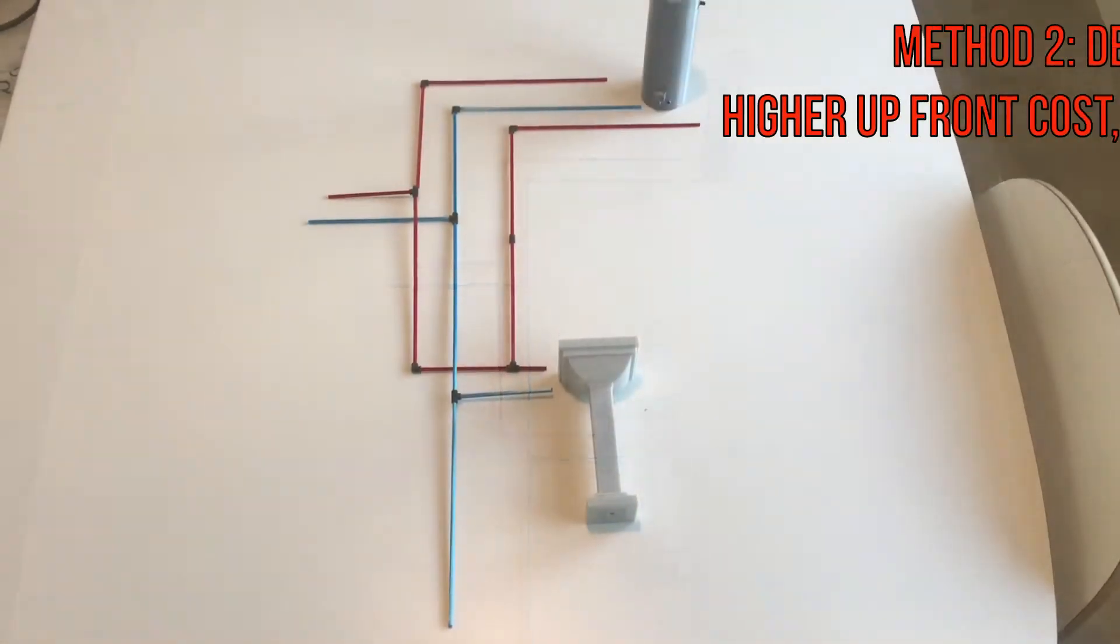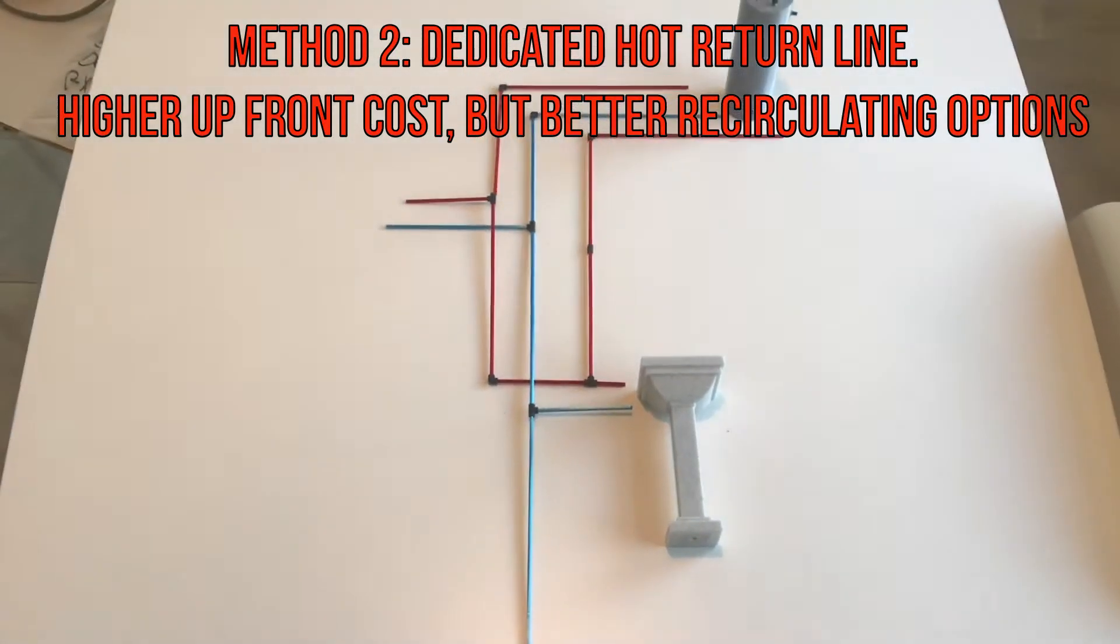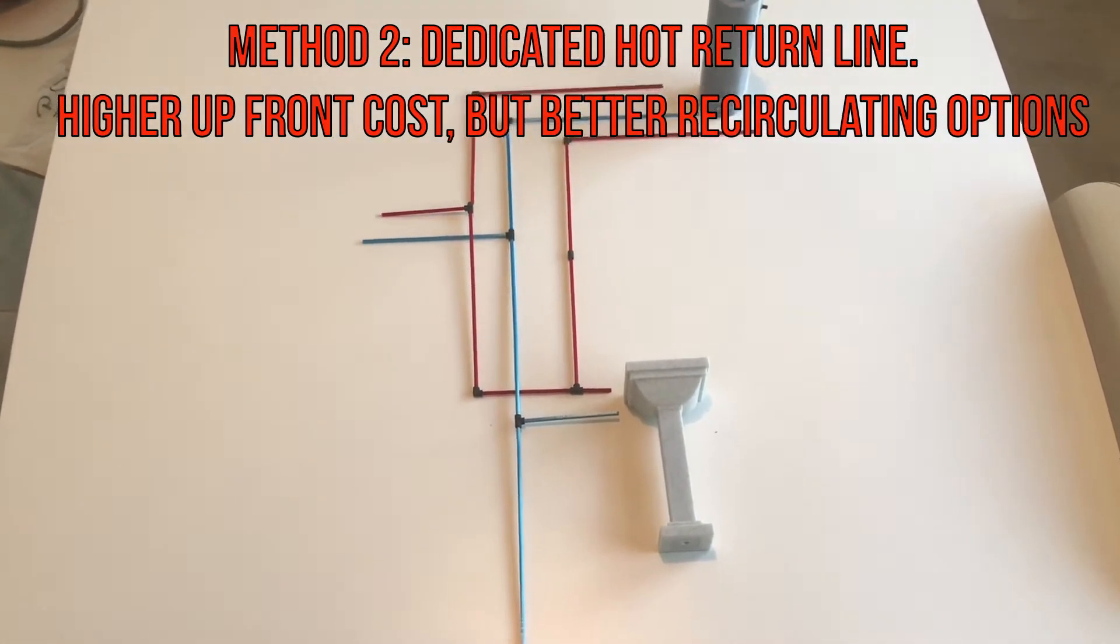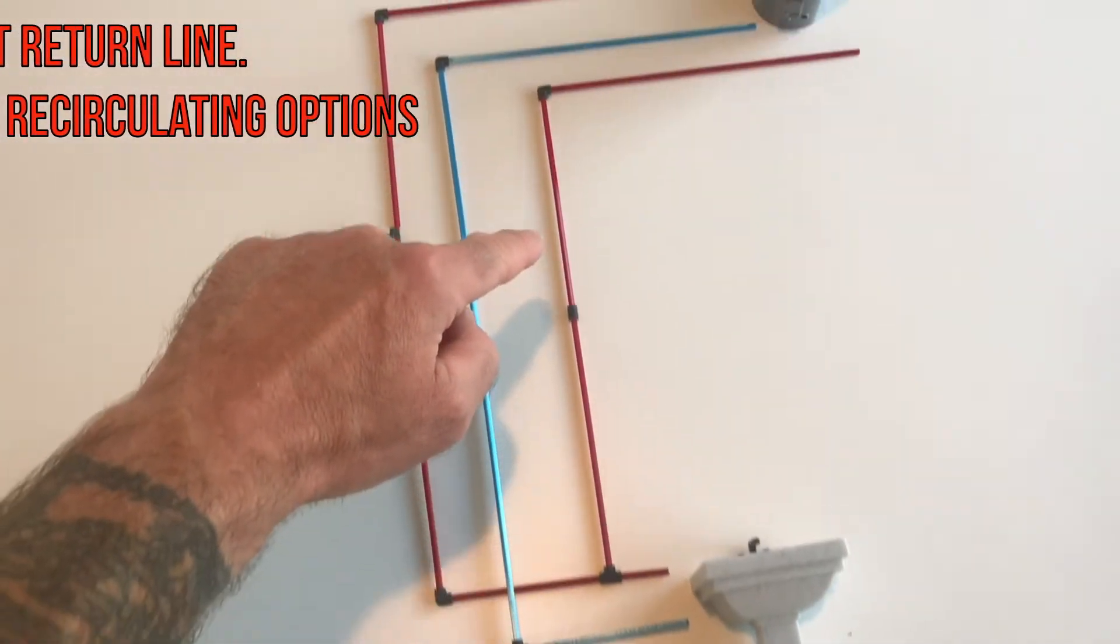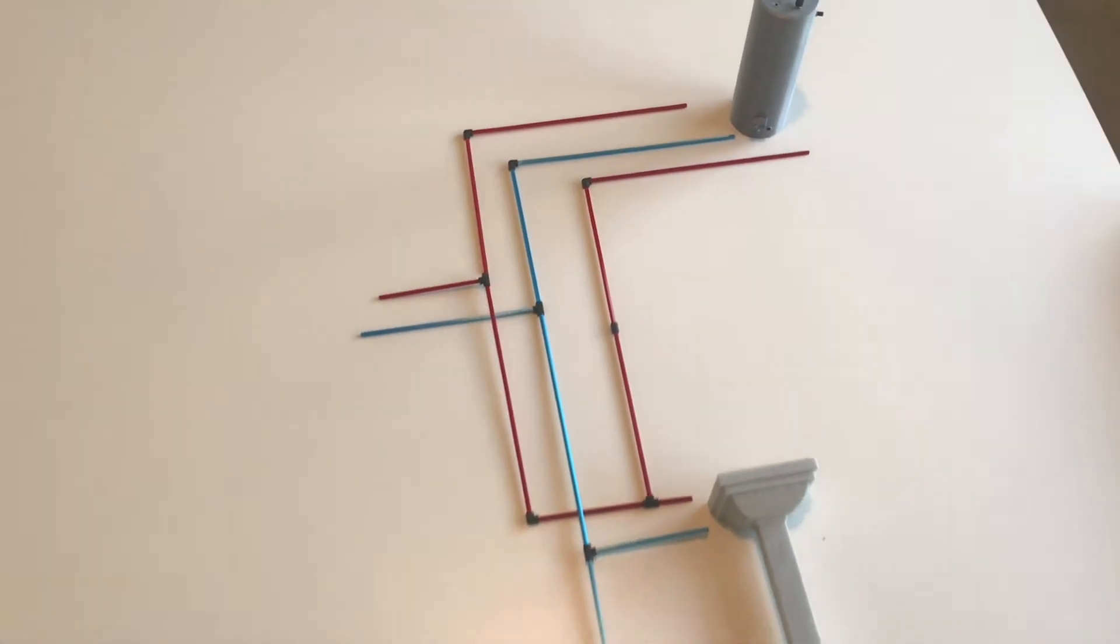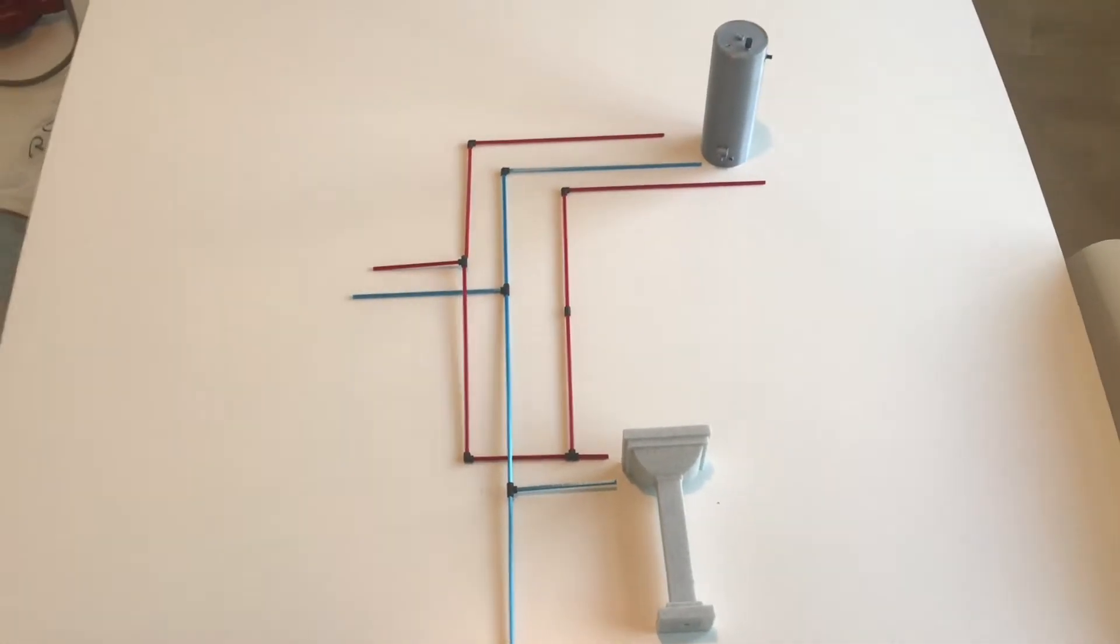If you have a traditional tank water heater and you have the opportunity to install a dedicated hot return line, which is this stretch of pipe here, this is the best method. It's my favorite method and if it's in a like a single story home and there's a crawl space and you can easily add the line it's well worth it.